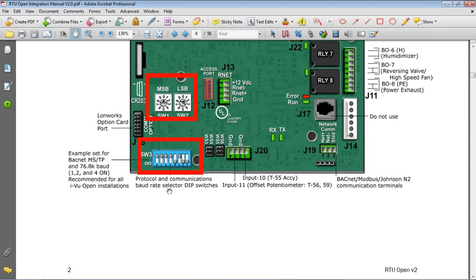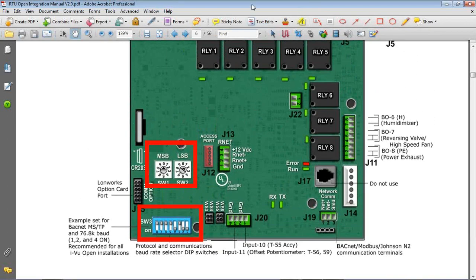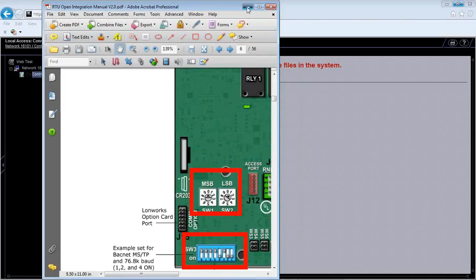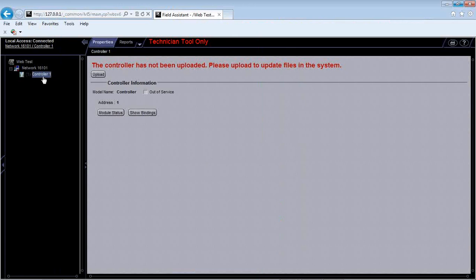But if you have different baud rates on different controllers, you're not going to be able to communicate properly either, because they're going to be trying to talk at different speeds. It's going to mess up your network, and you're not going to have success. So these are two critical things you want to set before you actually start programming and commissioning your controller. I've set my controller locally to address 1, and I'm at a baud rate of 76.8.